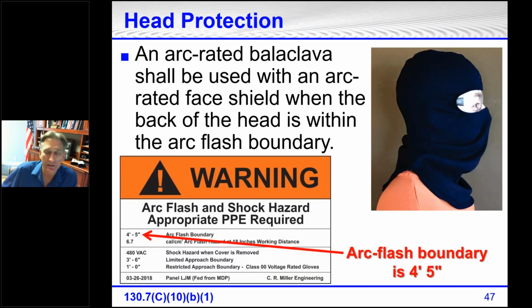So your question is, well, if I just wear a hard hat and face shield, is that okay? Do I have to wear the arc-rated balaclava? Well, here's your answer. An arc-rated balaclava has to be used with an arc-rated face shield when the back of your head is within the arc flash boundary.